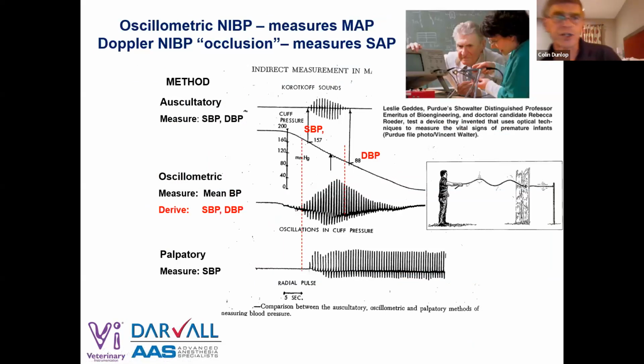So when we measure blood pressure with auscultation, we're looking at systole. With palpation, we're looking at the point where pressure returns, again, systole. This is what a Doppler is picking up. A Doppler is a pulse occluder. Oscillometric pressure determination is looking at these little oscillations, and it's looking for this midpoint in the oscillations, and that is the mean pressure. And what oscillometric is kind of doing is like this guy with his whip through the board where there's a hole, and the sine wave is turned into this little vibration, and it's that vibration that the machine is trying to pick up.